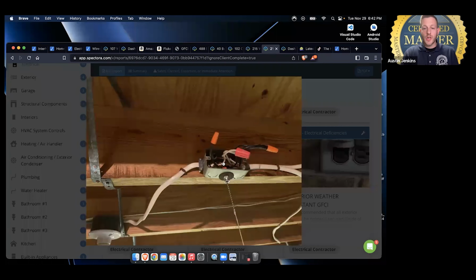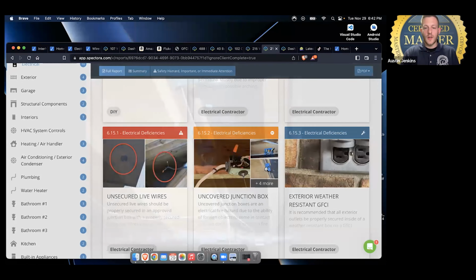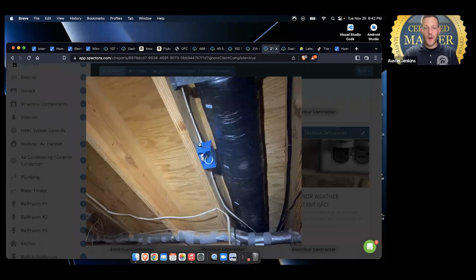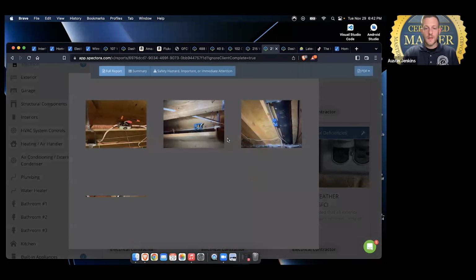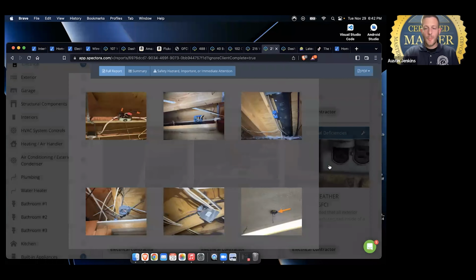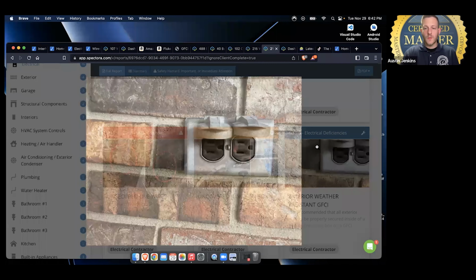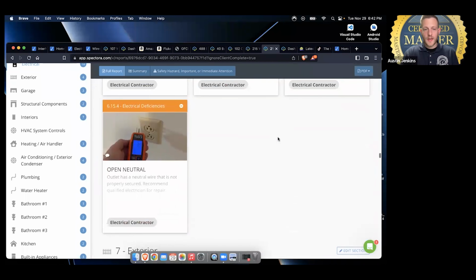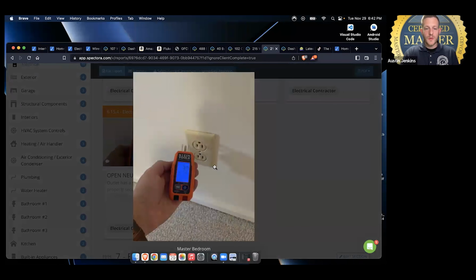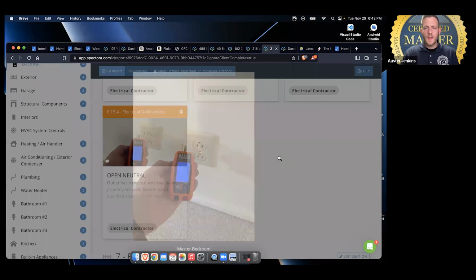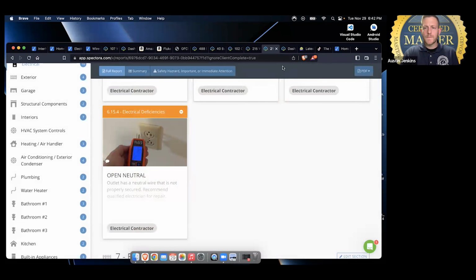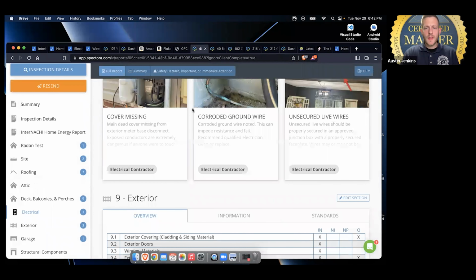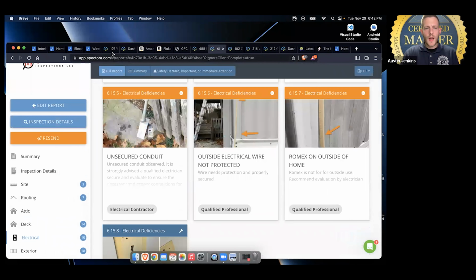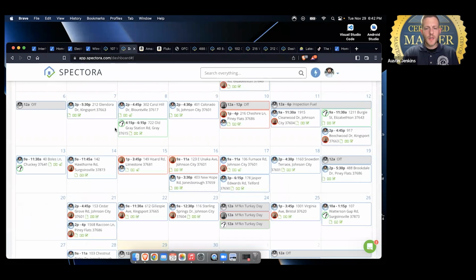We had some uncovered junction boxes. They just left the covers off of all of them. They installed the wiring and then just left the covers off. You can see those here. None of the outlets on the exterior were GFCI protected, so obviously that gets written up as well. And here we had an open neutral, and you can see that right here where it says open neutral. So going back, I think that covered all of the practical inspections.